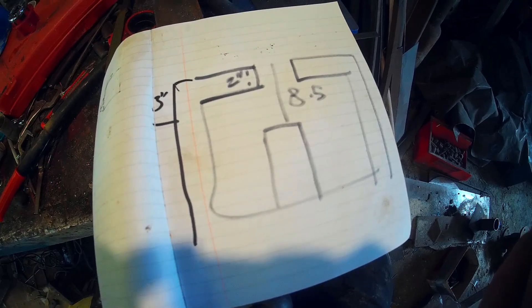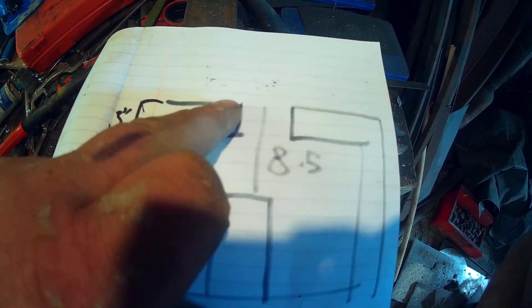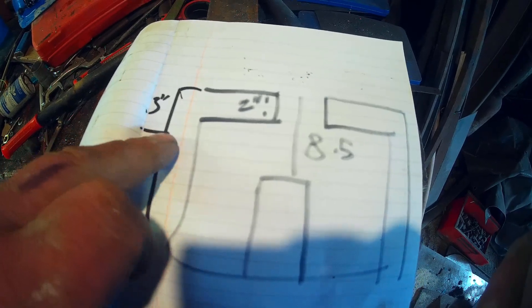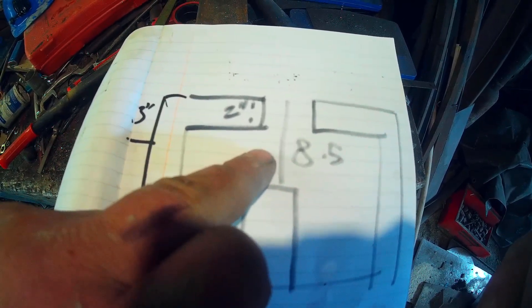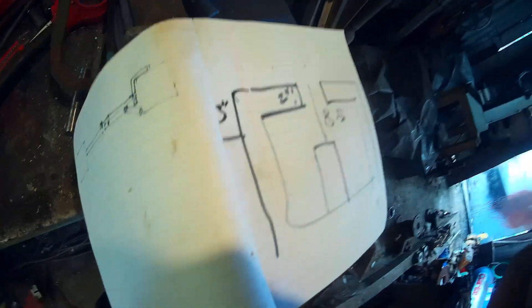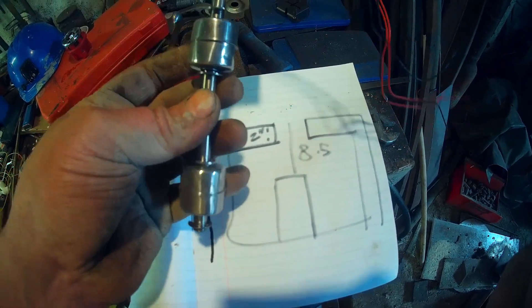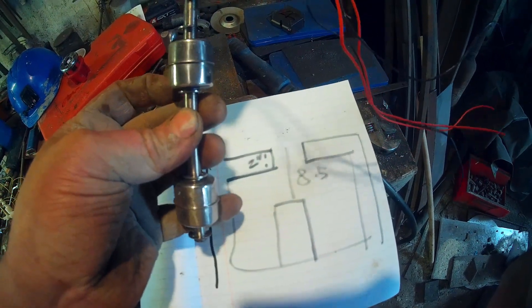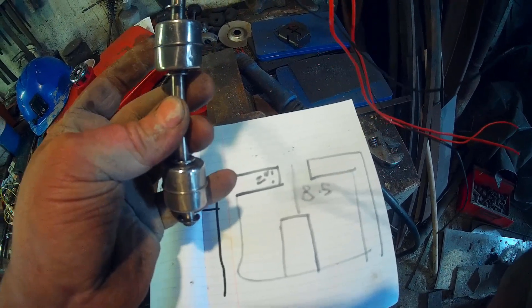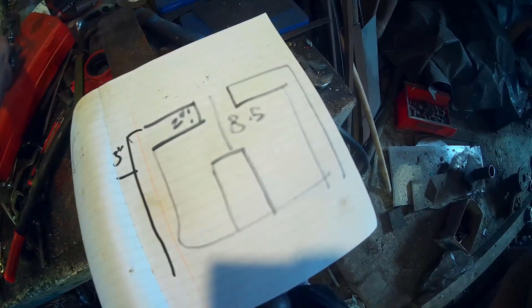So we're back out of the hole. On the workbench here — you can see from this diagram: top of the pump, then we've got eight and a half inches to the top of the sump. The sump is two inches thick and the limestone is three inches down the outside of the sump. So we've got five inches before things start flooding, and I'd ideally want to keep it lower than that. That means we can't use the nice stainless steel floats. This is a twin float design — the bottom one comes on, nothing happens; top one comes on, pump switches on; top one goes down, and the pump doesn't switch off again until the bottom one goes down. Just saves the pump flicking on and off too frequently and burning itself out.